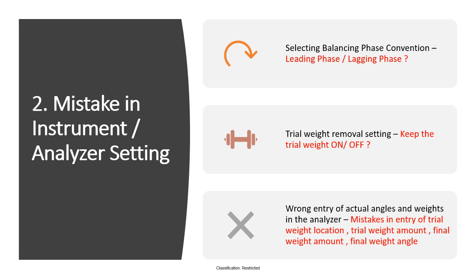Also critical is the correct entry of actual angles and weights in the analyzer. During startup of the balancing program, the trial weight location defaults to 0 degrees. Once you change the trial weight location from the reference point, you must enter the exact location and the exact amount of the trial weight, which also applies to the final weight amount and final weight angle.